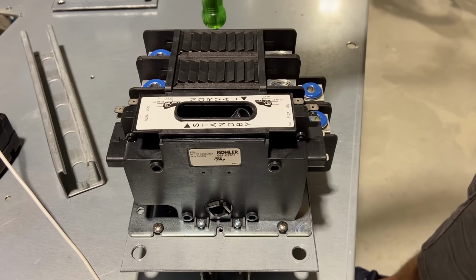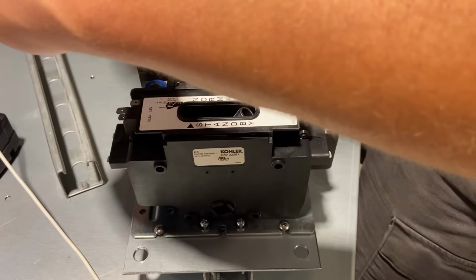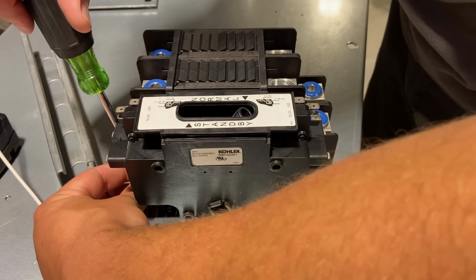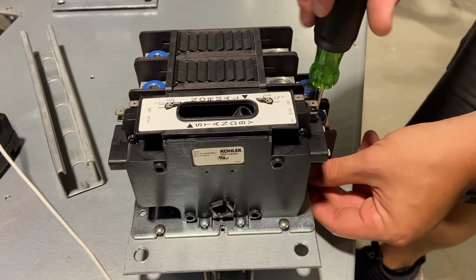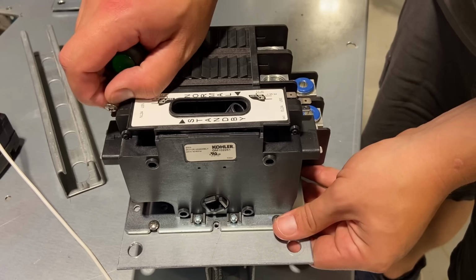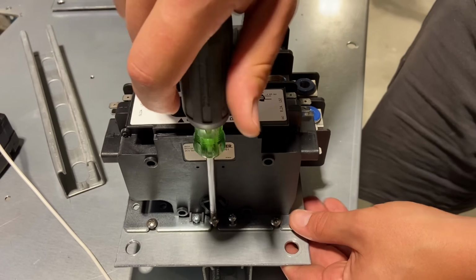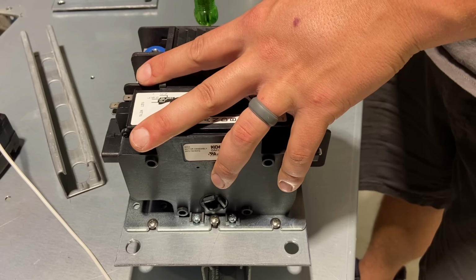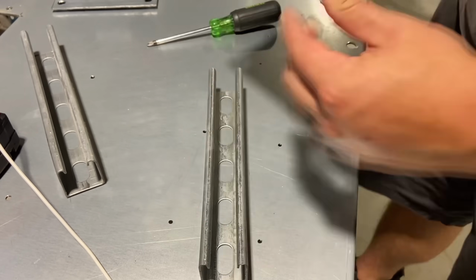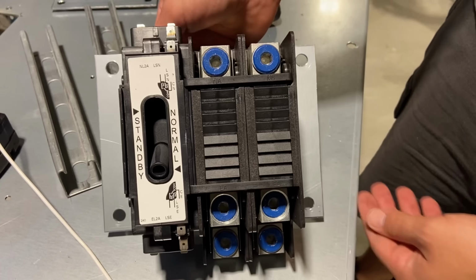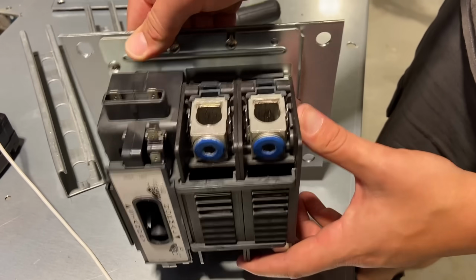I actually chose this transfer switch because of its simplicity. There's really not a lot going on here. You've got your 2 sets of coils for your normal and emergency transfer, you've got all your power, and then a few auxiliary contacts for the position of the switch. But really nothing too crazy. I do believe it's a 240 volt coil as well, which makes sense because that's what you're feeding into it.